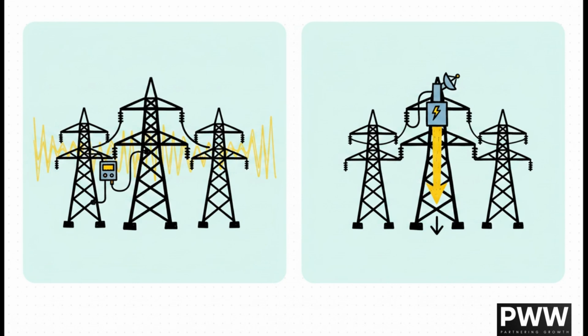If you use a regular low-frequency tester, it gives you a falsely low reading because the signal just travels straight down the overhead wires to adjacent towers. High-frequency testing, on the other hand, mimics the high-frequency nature of a real lightning strike. A lightning strike happens so incredibly fast that the affected tower acts as if it's electrically isolated anyway. Measuring the true isolated footing resistance gives utilities the exact, accurate data they need for optimum lightning protection design.